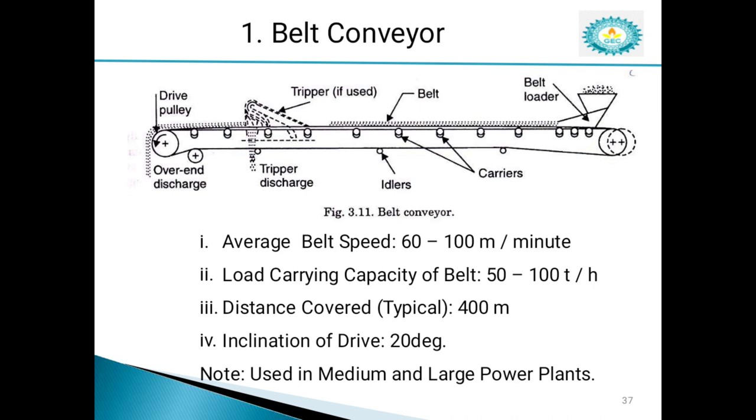Specifications are: the belt speed is 60 to 100 meters per minute, and load carrying capacity is 50 to 100 tons per hour. Distance covered is typically 400 meters, and inclination of drive is 20 degrees. This type of conveyor is used in medium and large power plants.